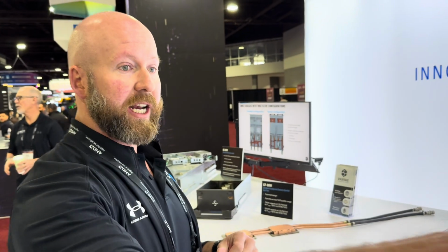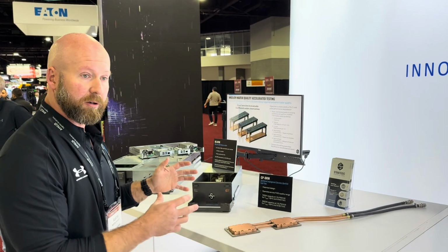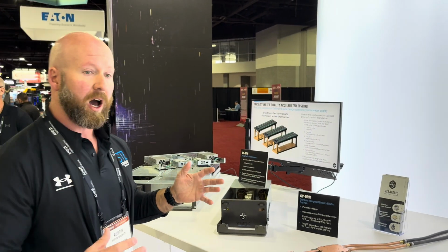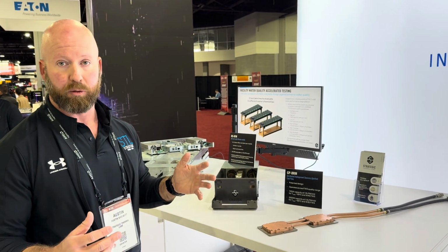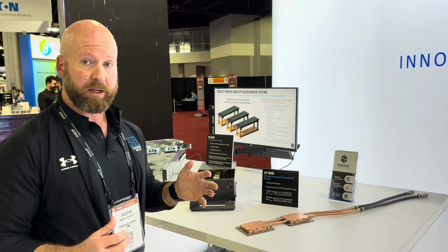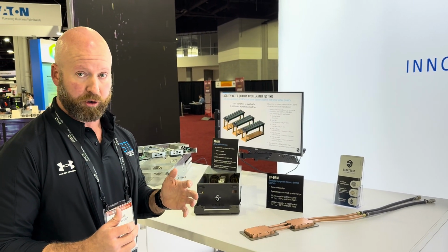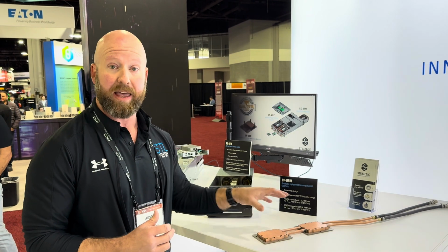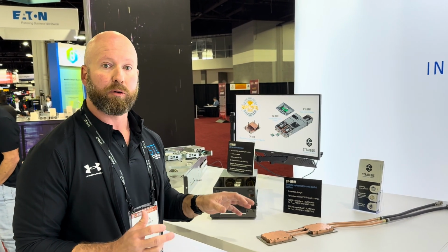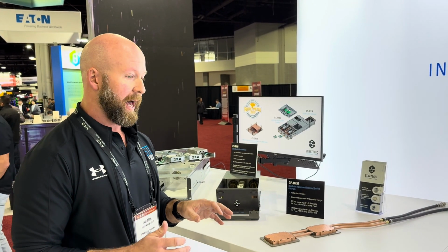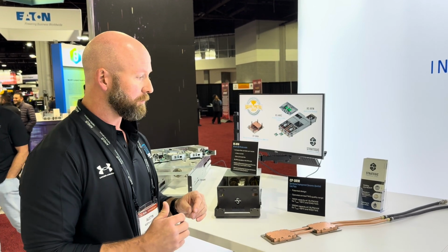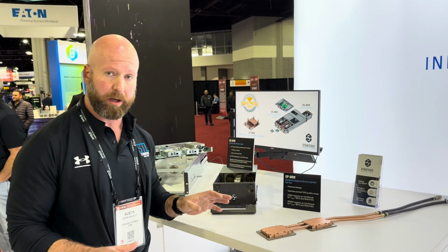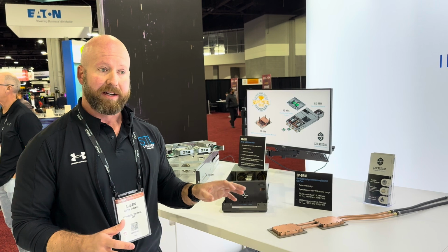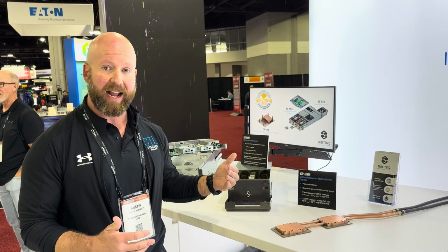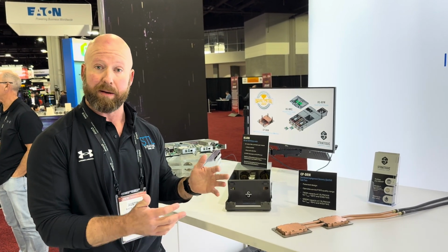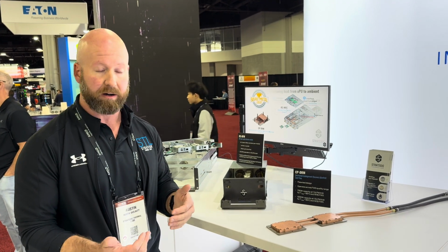So we're selling CDU solutions, but we're also leading the charge on a new type of cooling called bare metal liquid cooling. Bare metal liquid cooling is a non-CDU cooling solution where we design the cold plates and the rack infrastructure to operate directly on facility water supply, bypassing CDU entirely. This type of cooling solution is not for everyone. This type of cooling solution is for data centers that have fairly advanced water quality control mechanisms already in place in their facility or intend to get there.